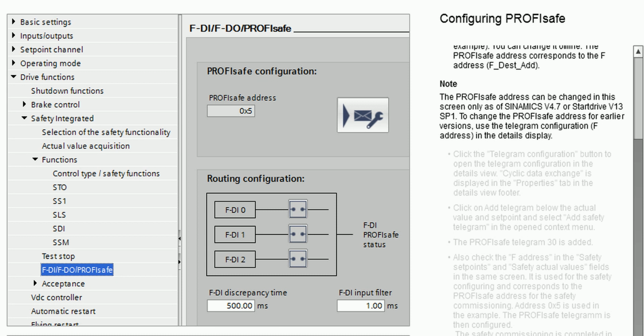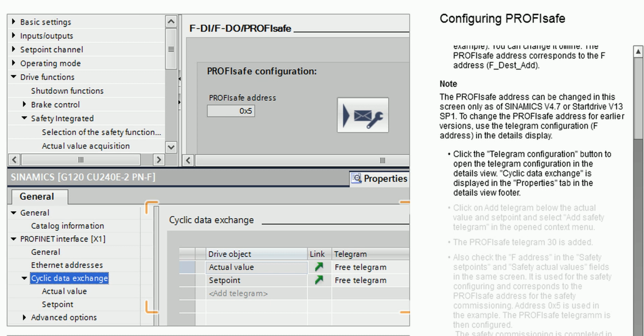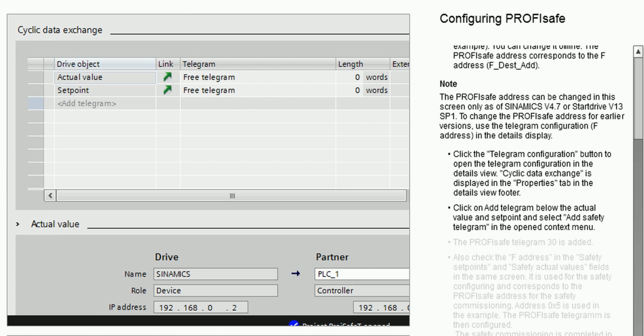Note: the PROFIsafe address can be changed in this screen only as of SINAMICS V4.7 or Startdrive V13 SP1. To change the PROFIsafe address for earlier versions, use the Telegram configuration, F address, in the details display. Click the Telegram configuration button to open the Telegram configuration in the details view. Cyclic Data Exchange is displayed in the Properties tab in the Details view footer. Click on Add Telegram below the actual value and setpoint and select Add Safety Telegram in the open context menu.